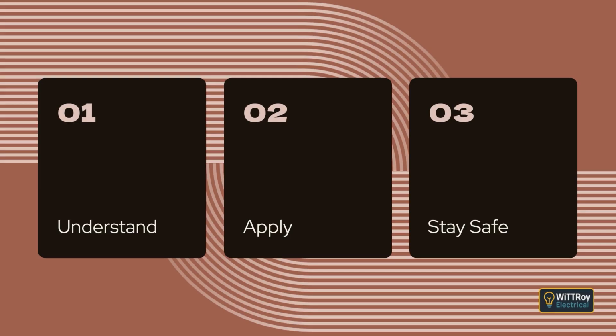Clause 4.10.5 Additional protection. All heating cables shall be provided with additional protection by an RCD with a fixed residual current not exceeding 30 mA, and in the case of heating units fitted with a conductive covering, this covering shall be earthed, and in the case of underfloor heating units without a conductive covering, an earthed metallic grid with a spacing not exceeding 30 mm shall be provided above the underfloor heating cable, and heating units shall be provided with adequate mechanical protection to prevent damage.